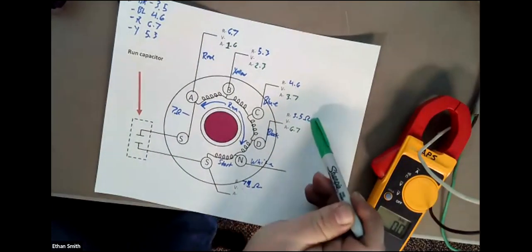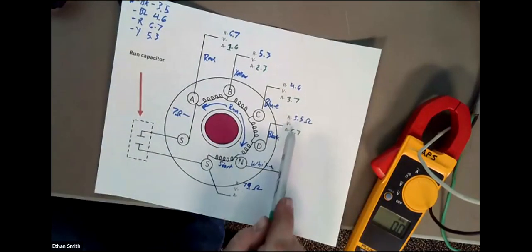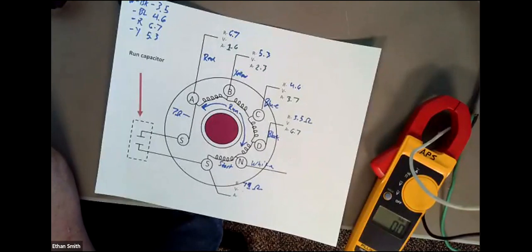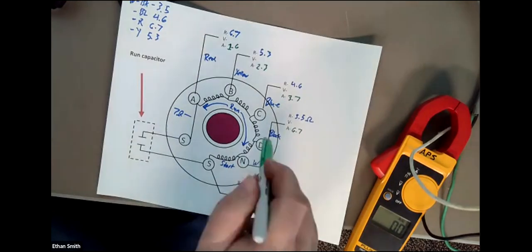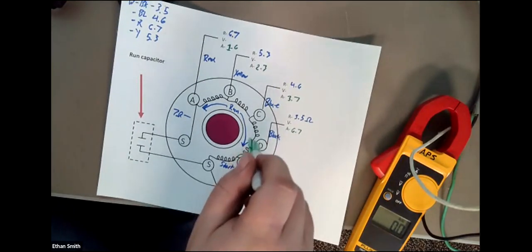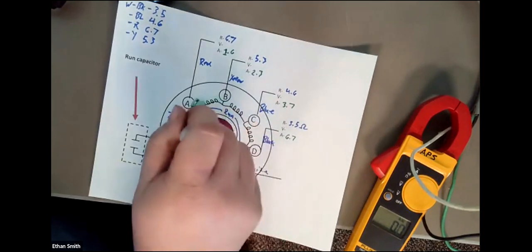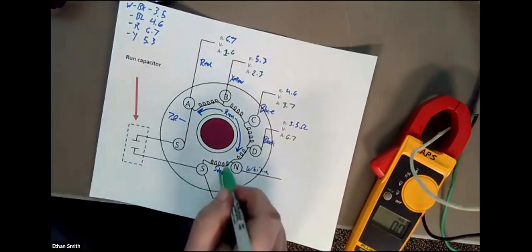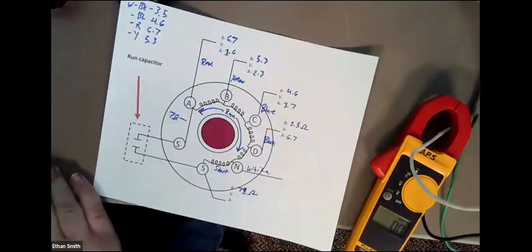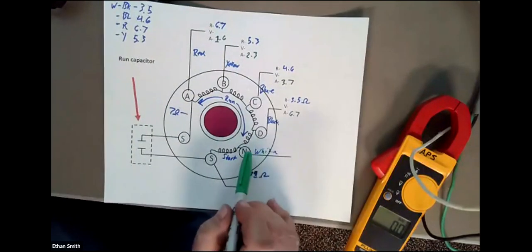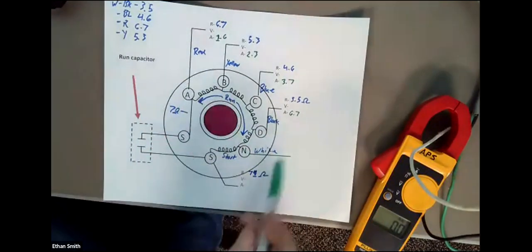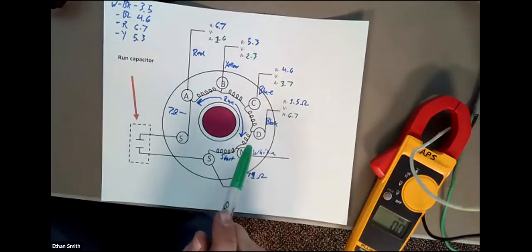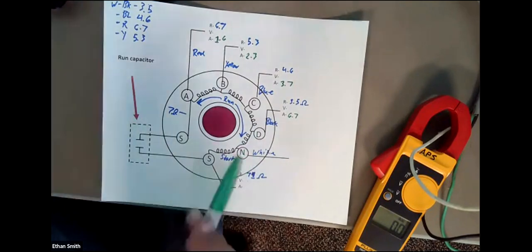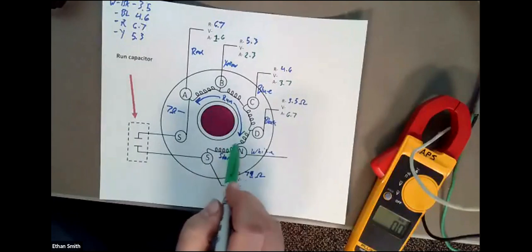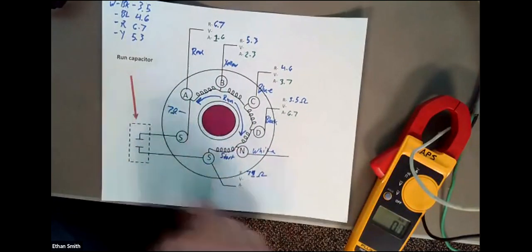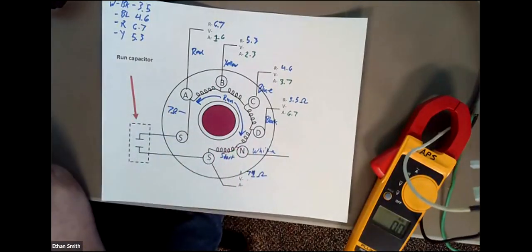So yes, your lowest resistance reading is going to be your highest speed because that's going to create the most current for you. Now, something interesting that happens here is when you put your neutral in here, your run winding becomes just this little section of wire right here. All of this actually gets added to your start winding because now it's out of the main circuit and it's in the start winding circuit. Whereas if we have my neutral to red, we give up some speed, but we operate at a lower speed, and that's assisted by the fact that we don't have as much start winding anymore. Because now I'm utilizing this whole winding as my run, and my start winding is just this little section down here. Any questions?